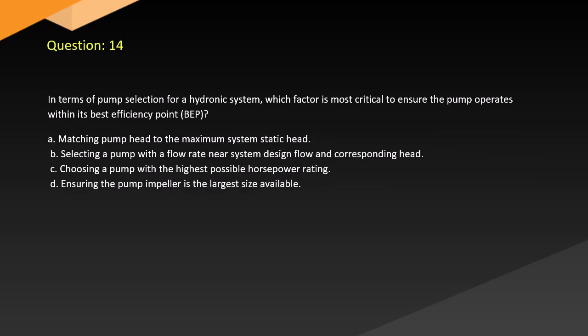Question 14. In terms of pump selection for a hydronic system, which factor is most critical to ensure the pump operates within its best efficiency point? A. Matching pump head to the maximum system static head. B. Selecting a pump with a flow rate near system design flow and corresponding head. C. Choosing a pump with the highest possible horsepower rating. D. Ensuring the pump impeller is the largest size available.